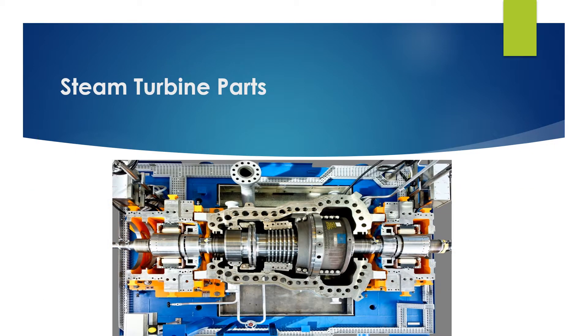The steam turbine and compressor setup consists of a shaft and rotating plates to capture the energy from the steam. This simplicity ensures that maintenance is low-cost and easy. This equipment can be converted to produce electricity by transferring the work from the steam to a generator rather than a compressor. The dual functionality of this process allows for cost-effective changes to plant production.